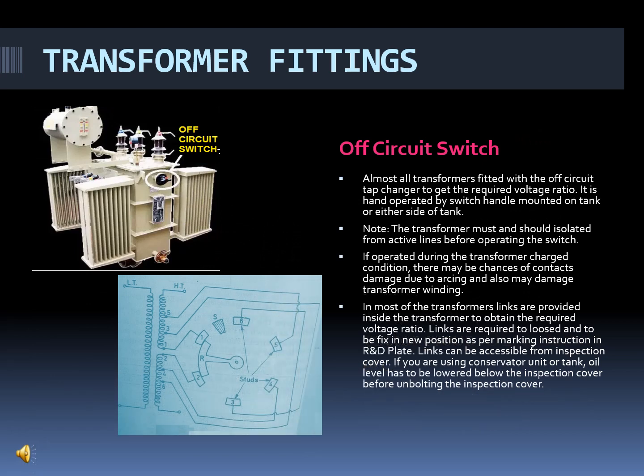The second fitting of the transformer is the off-circuit switch. Almost all transformers are fitted with the off-circuit tap changer to get the required voltage ratio. Every customer requires a particular voltage ratio for their circuit, so almost all transformers contain the off-circuit tap changer switch. It is hand operated by a switch handle mounted on the tank, on either side of the tank. See, I have enclosed the image.